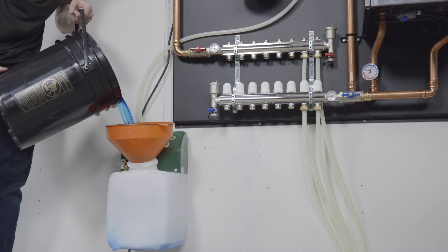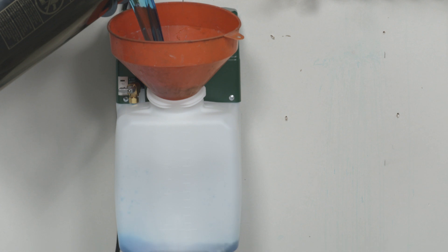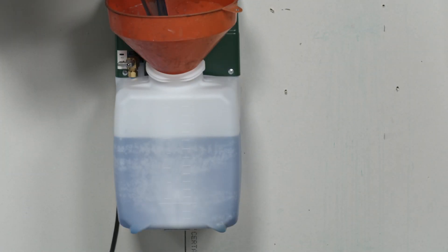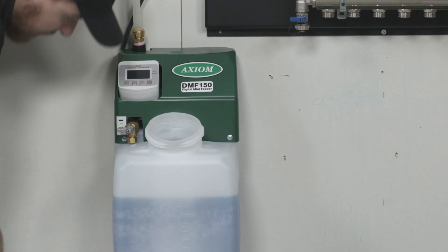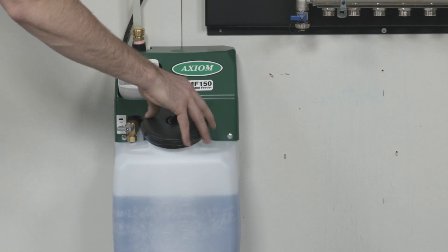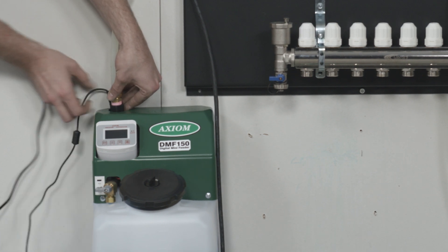With a funnel, fill the glycol feeding system with water and glycol. We recommend diluting the glycol to 50/50 or greater to fill the system, with a targeted end result of 30 to 35 percent glycol as the final fill. Plug the glycol feeder into an outlet.